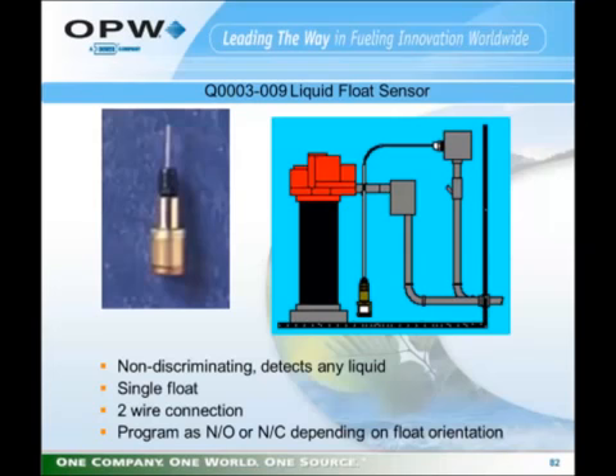The Q0003-009 liquid float sensor is simply a magnetic float switch type sensor. It is open or it is closed. It's non-discriminating, detects any liquid. It is a 2-wire connection, and it is programmed as either normally open or normally closed depending on the float orientation. Usually it is shipped as a normally closed sensor.